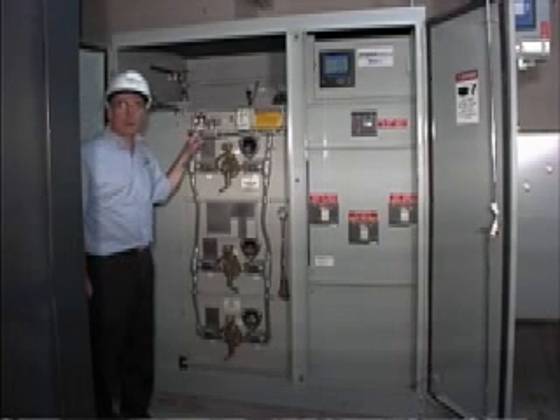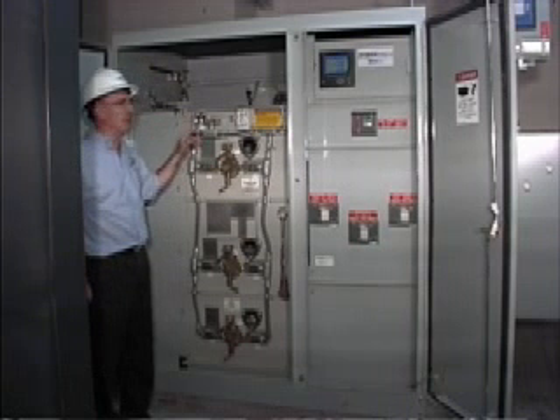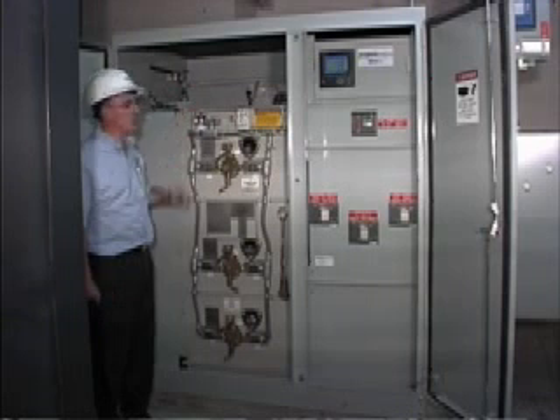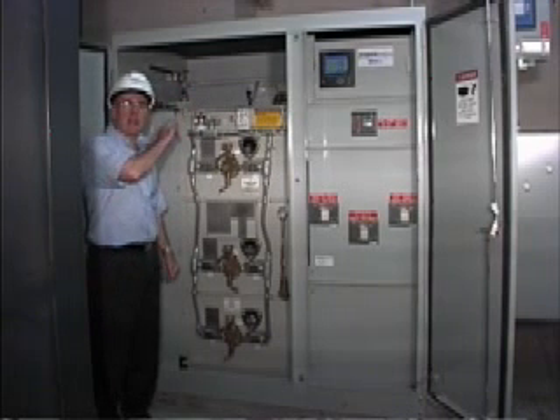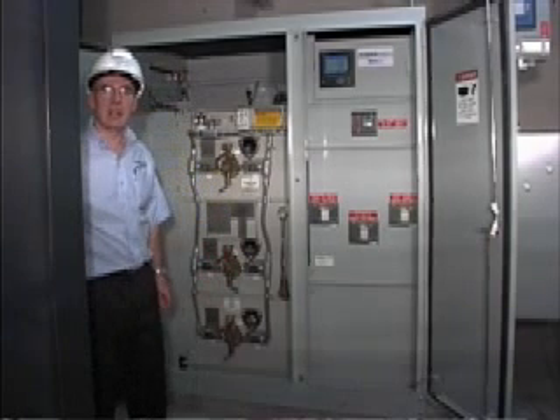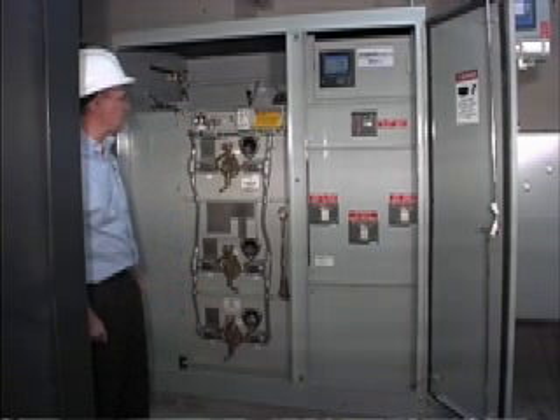When the pressure drops below three pounds, this will close this contact and will be indicated on their digital meter up here. There are also two gauges in the back which will give you the oil level and oil temperature. Certain contacts in there will also be closed to give you an indication on the SCADA system.